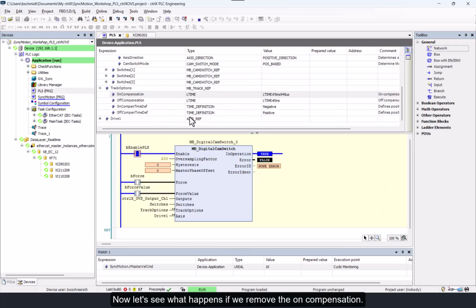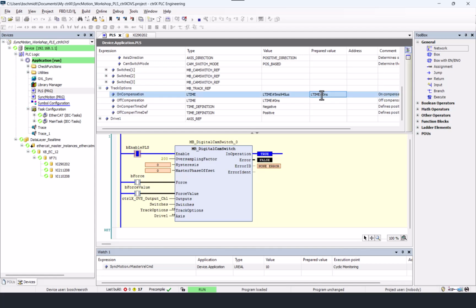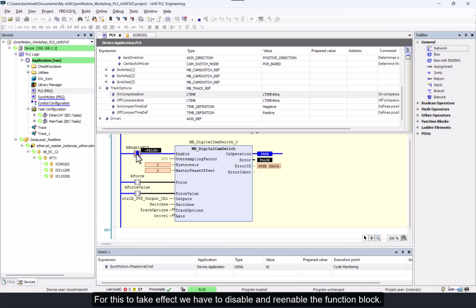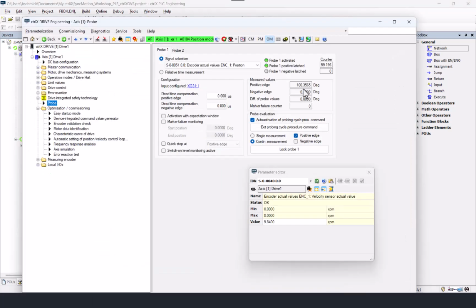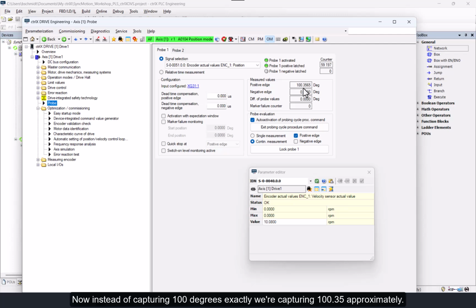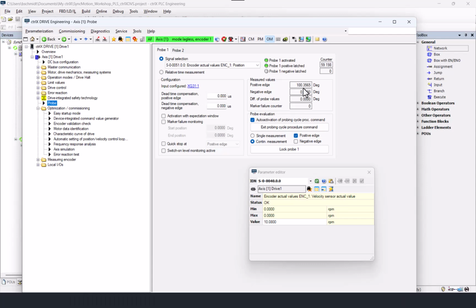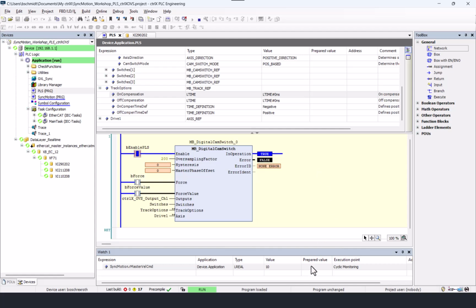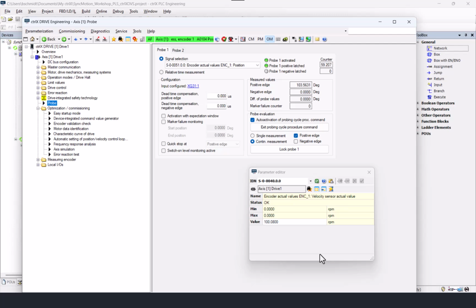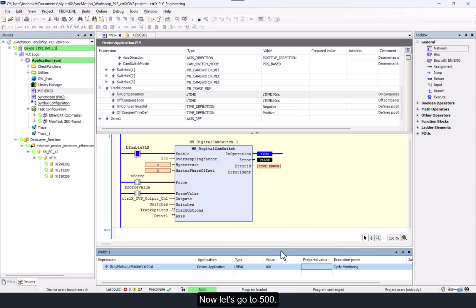Now let's see what happens if we remove the on compensation. For this to take effect, we have to disable and re-enable the function block. So now instead of capturing 100 degrees exactly, we're capturing approximately 100.35. Let's go up to 100. Now it's 103.56. Now let's go to 500.